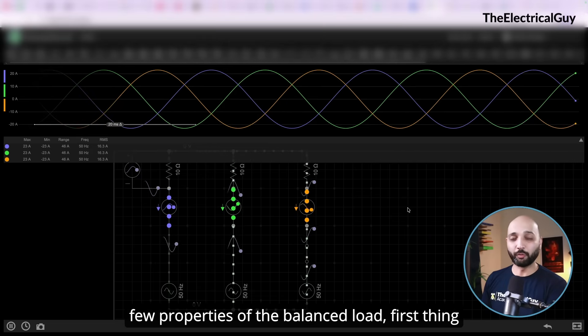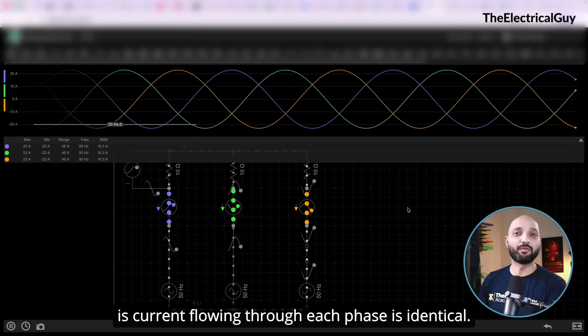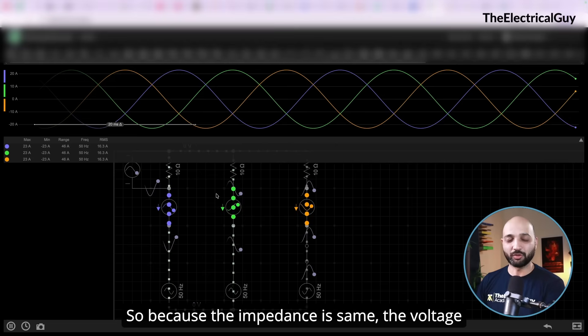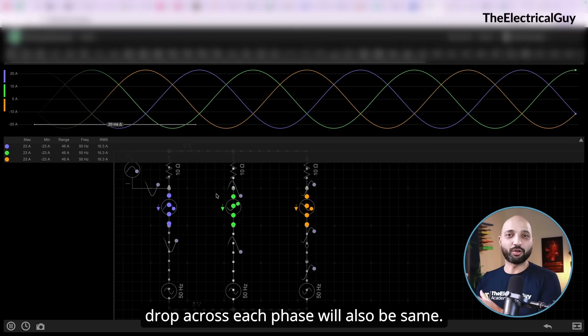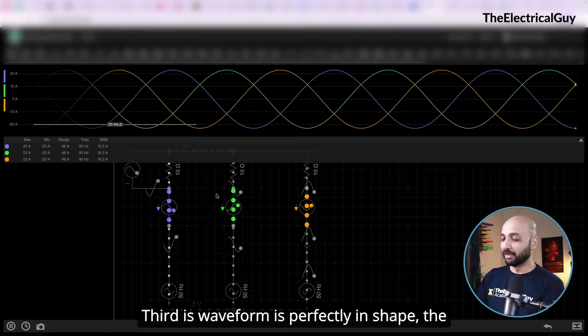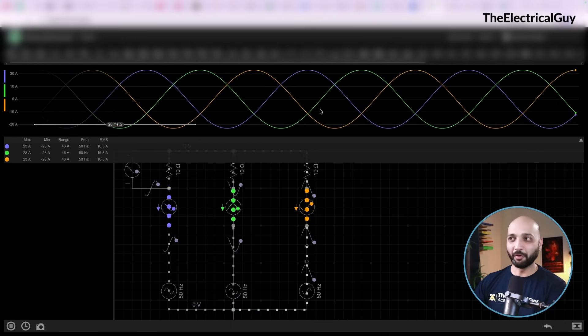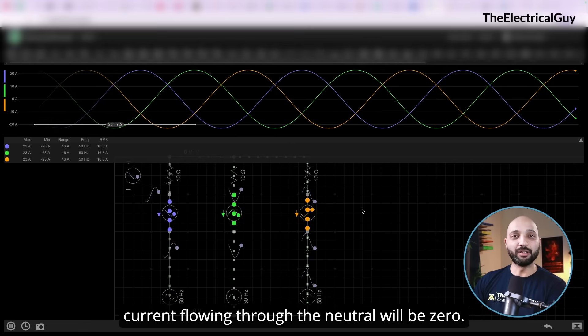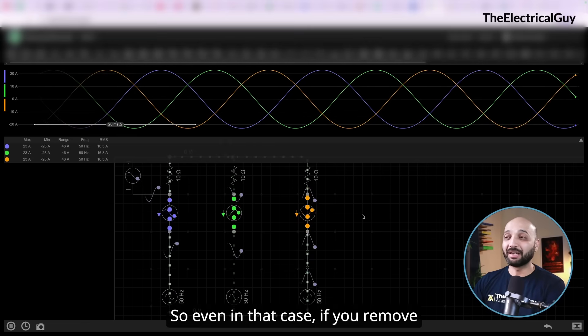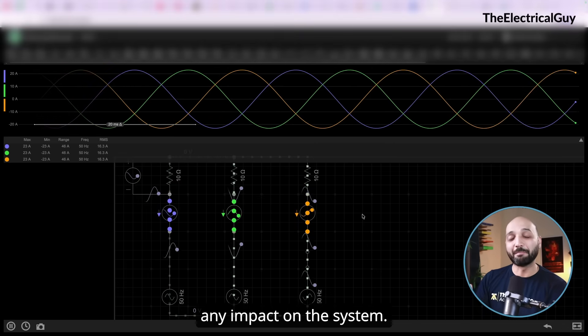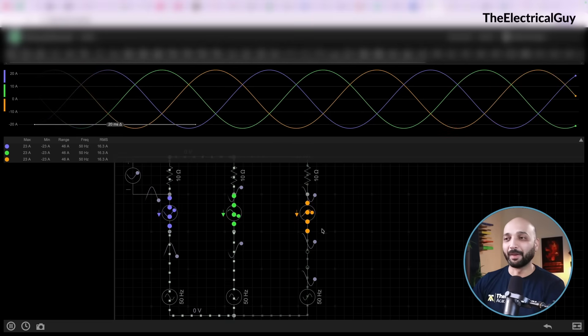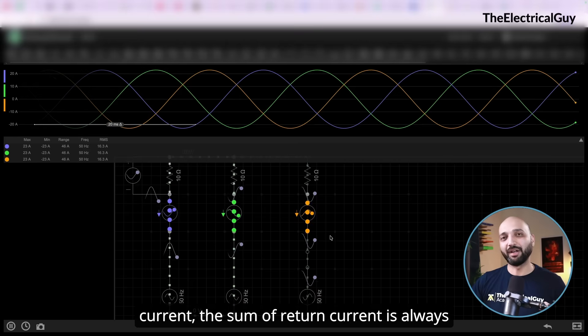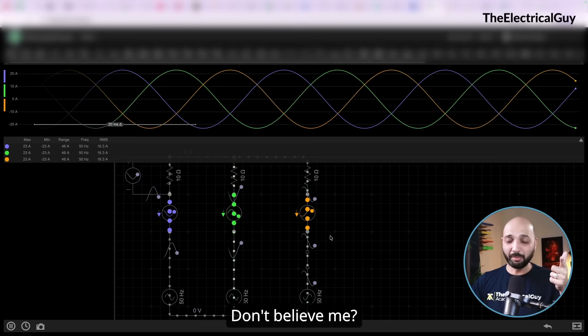The properties of a balanced load are: first, the current flowing through each phase is identical; second, the voltage across each phase is the same — because impedance is the same, the voltage drop is equal; third, the waveform is a perfectly shaped sinusoid; and fourth — the most important — the current flowing through the neutral will be zero. Even if you remove the neutral wire completely, there will be no impact on the system.